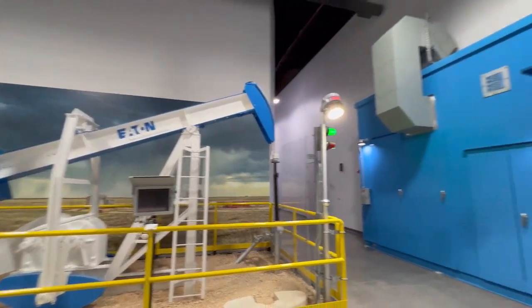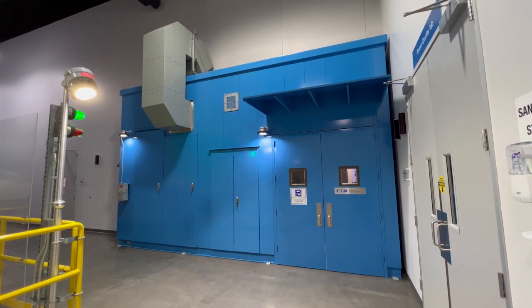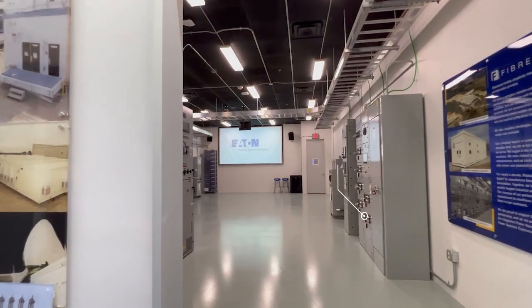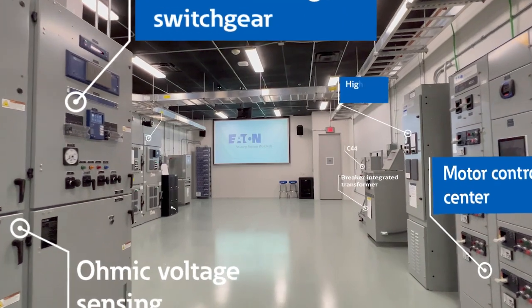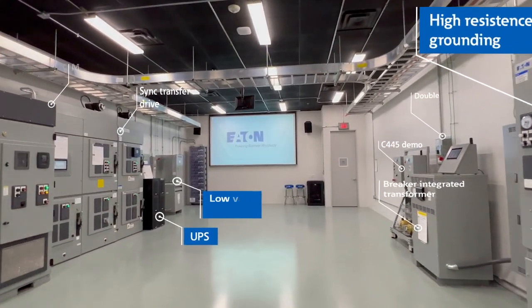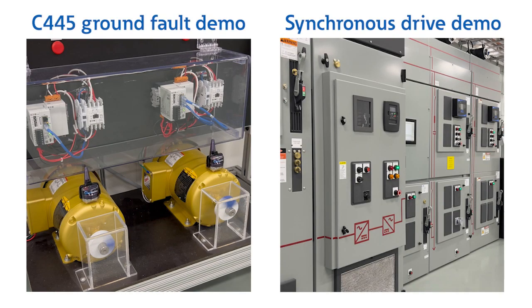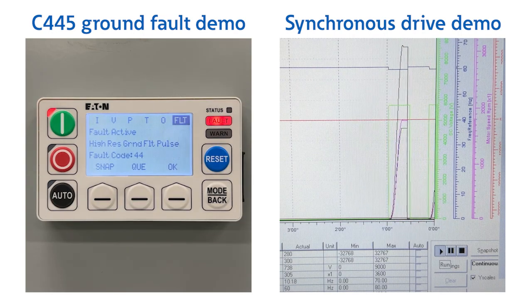Next to the pump jack, you'll find that we have installed our very own e-house. Also called an integrated power assembly (IPA), this is a fully customizable, prefabricated building that contains industrial control and power distribution equipment. If you step inside our e-house, you'll see distribution and control equipment including a low-voltage motor control center, medium-voltage switchgear, a high-resistance ground, UPS, low-voltage panel boards, and battery storage. Our two most popular demonstrations in this space are the C-445 ground fault detection and the medium-voltage synchronous transfer drive.